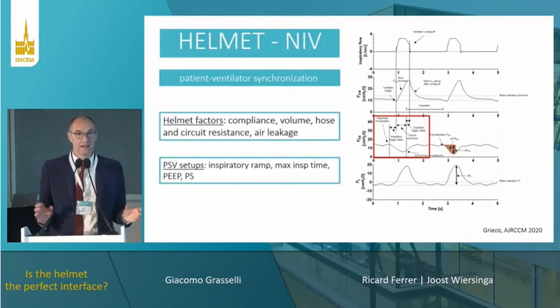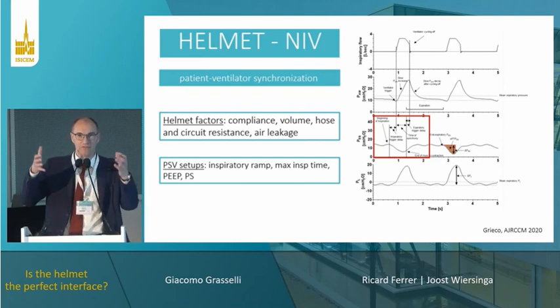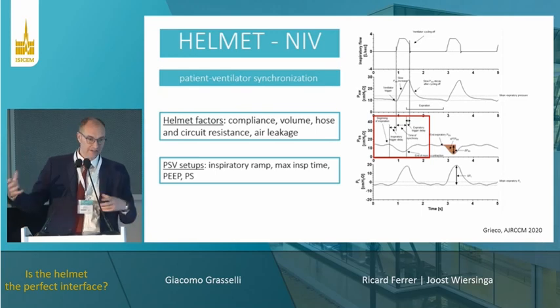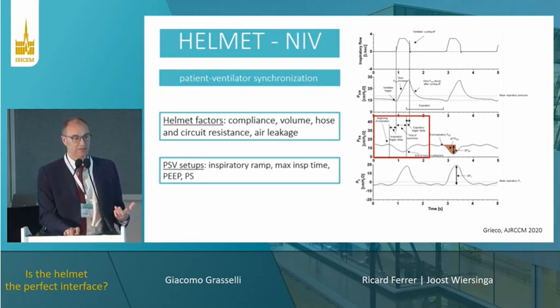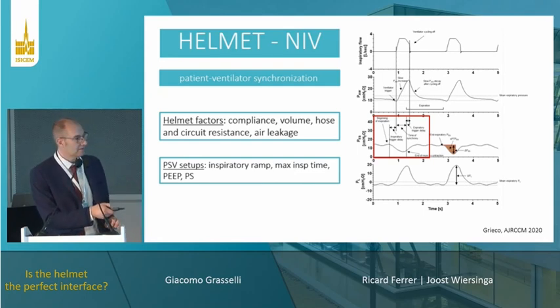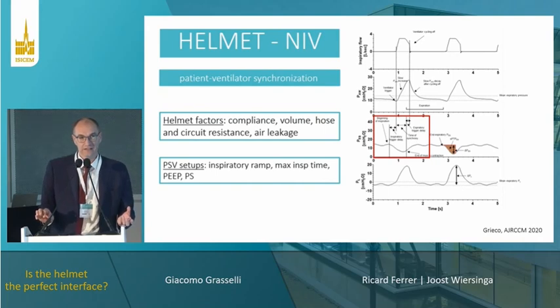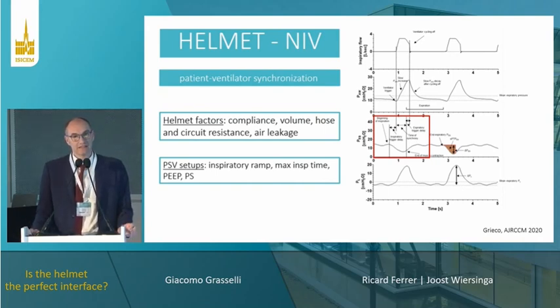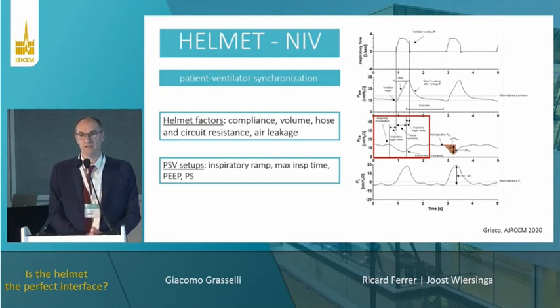Indeed, this is true. I mean, the helmet has a certain high compliance, so it needs time to inflate the helmet. It has a large volume. There is resistance of the circuit, and so this turns into bad synchronization between the patient and the ventilator. So from the moment when the patient starts the inspiration to the moment when the ventilator actually delivers the assist, there is a huge inspiratory trigger delay. And we all think that when you are receiving an assisted mode of ventilation, it's very important that the patient and the ventilator are synchronized.